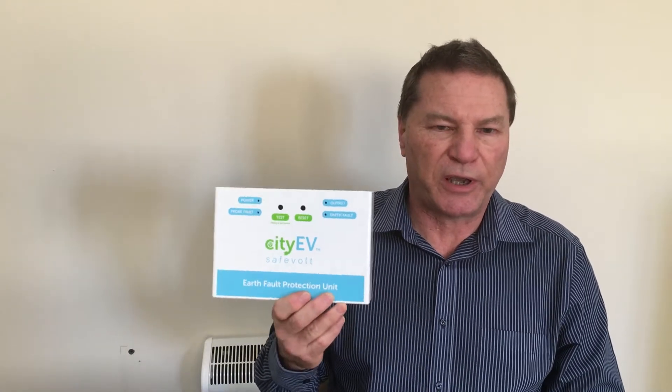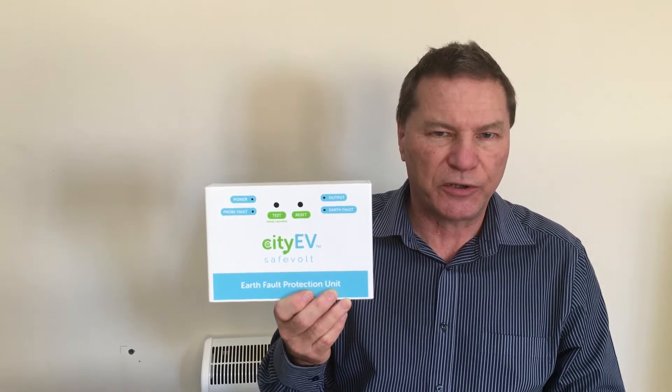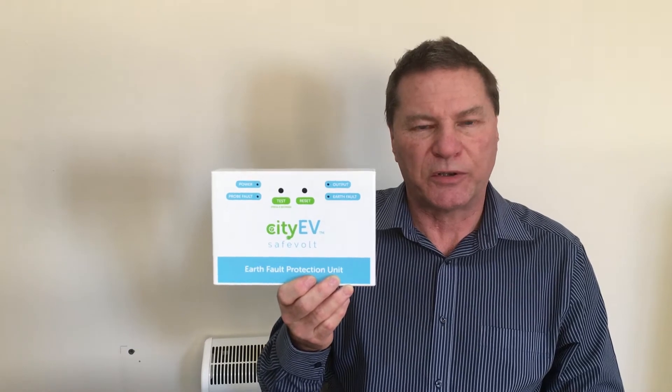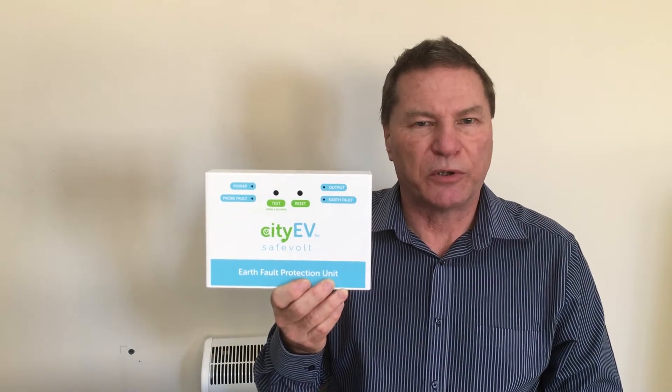The cityEV SafeVolt is able to perform the functions of both indent 3 and indent 4. It can operate with a sensing probe, making it suitable for three-phase charge point installations. It can also work in the mode where it senses the line voltage rather than the probe voltage, making it suitable for simpler single-phase charge point installations.